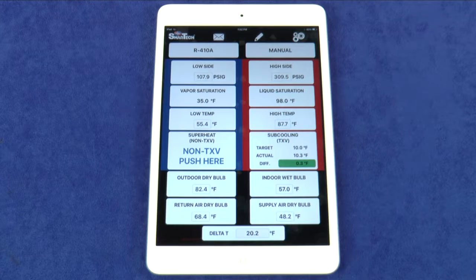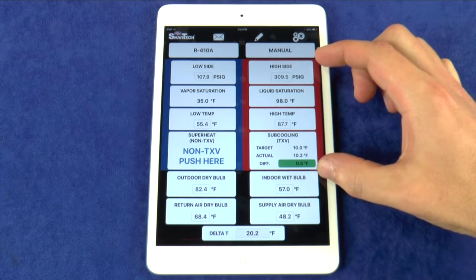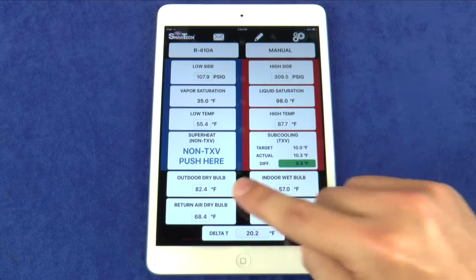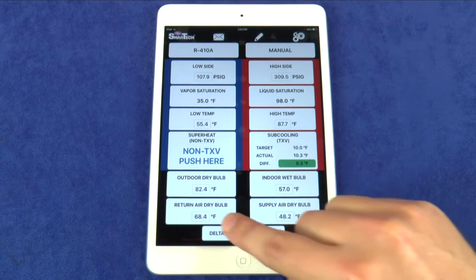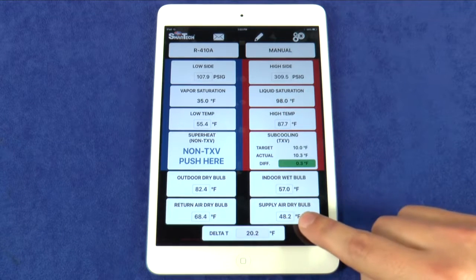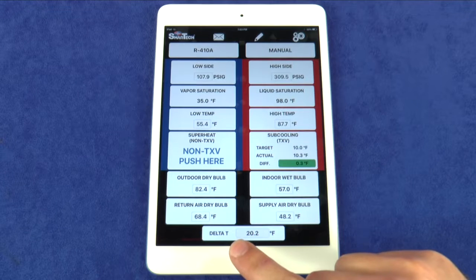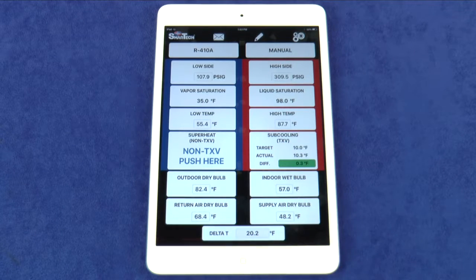This makes it very easy to get the perfect system charge for maximum efficiency and optimal performance. All of the fields we have looked at so far are auto-populated by the Uniweld manifold. These four fields at the bottom require manual data entry: the outdoor dry bulb, indoor wet bulb, return air dry bulb, and supply air dry bulb. The delta split will be auto-calculated when the return air dry bulb and the supply air dry bulb are entered.